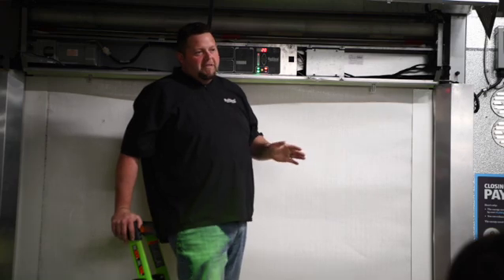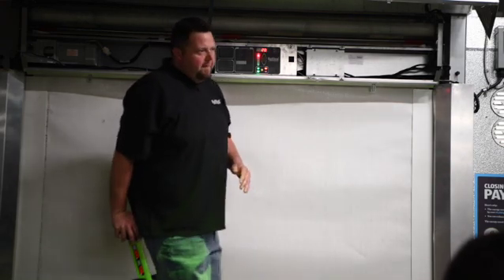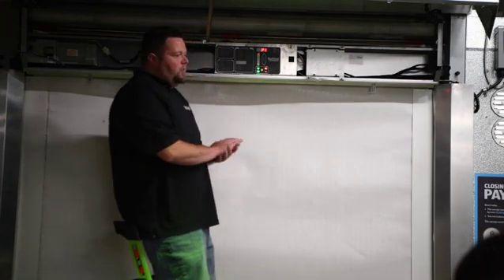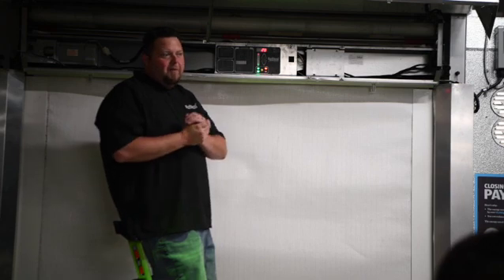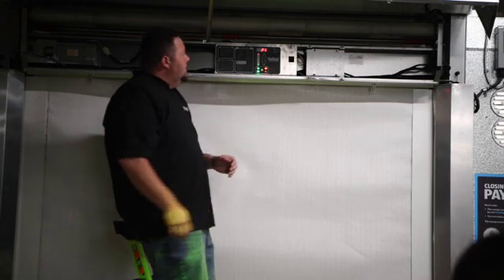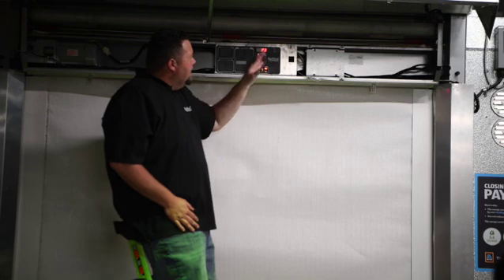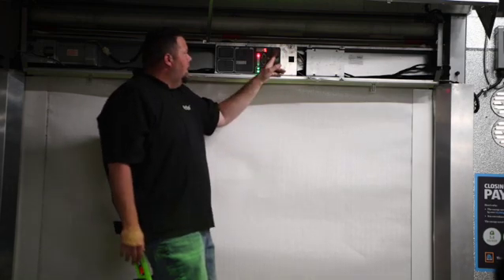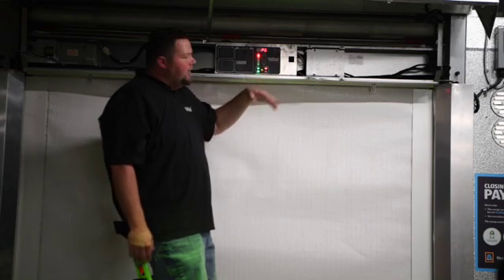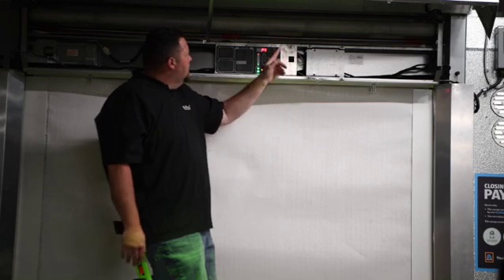You have a full ability to change that. Aldi spec is 20 seconds. So leave it at 20. If there's special occasions or whatever else, I guess you work it out with them, but that is an Aldi spec. So when we change that, P3 is the deceleration range. It's on 5 right now. You're never really going to mess with it. It's going to come on 0. So we'll put it back on 0, but you're never going to mess with that. That's not anything y'all are going to ever need to mess with.